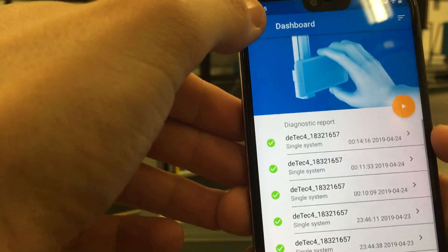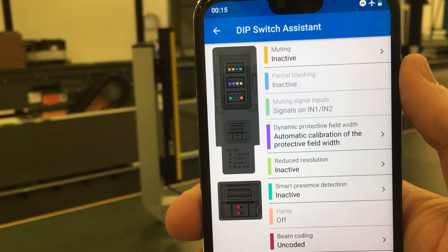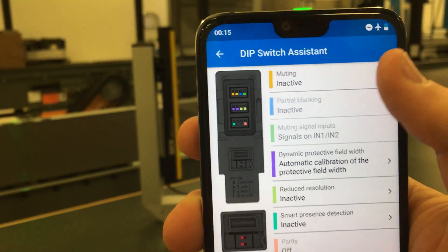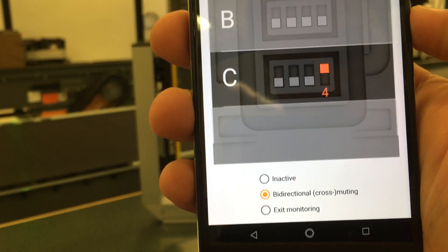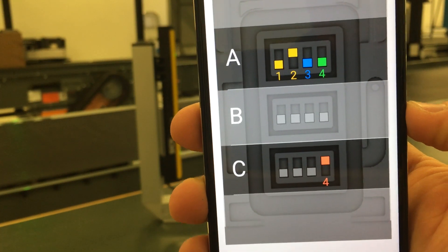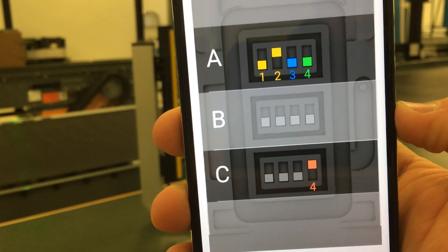Another cool feature is if you go back into the menu, you can go to the dip switch assistant. As you may know, everything in the new deTec4 safety light curtain is dip switch configurable. So if I want to turn on the muting or cross-muting feature, I turn it to active, and now you can see it displays exactly how I should be setting my dip switch in the system plug for the safety light curtain.